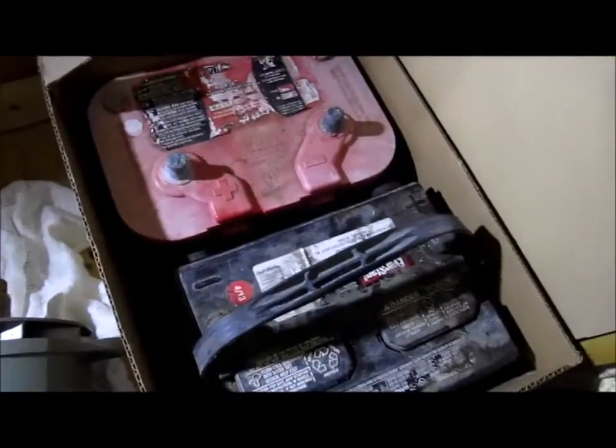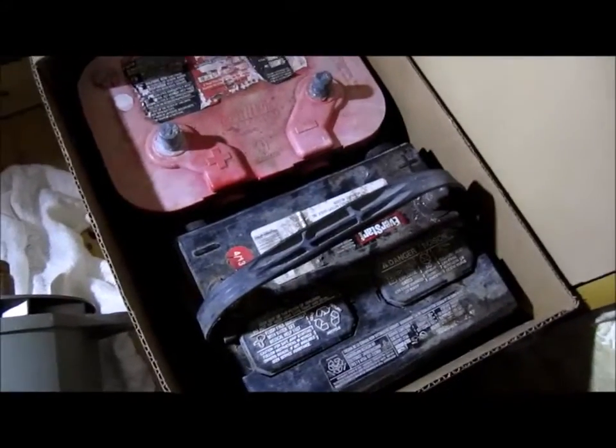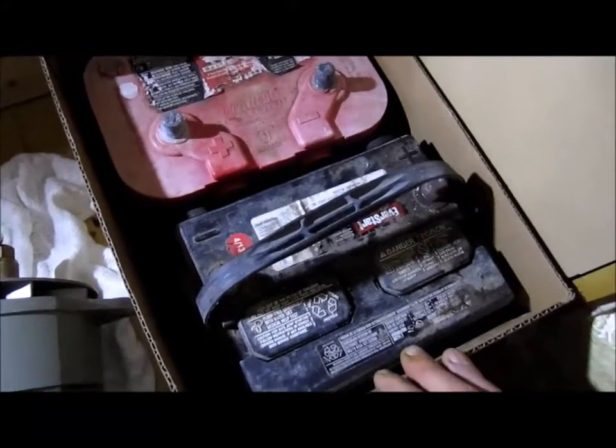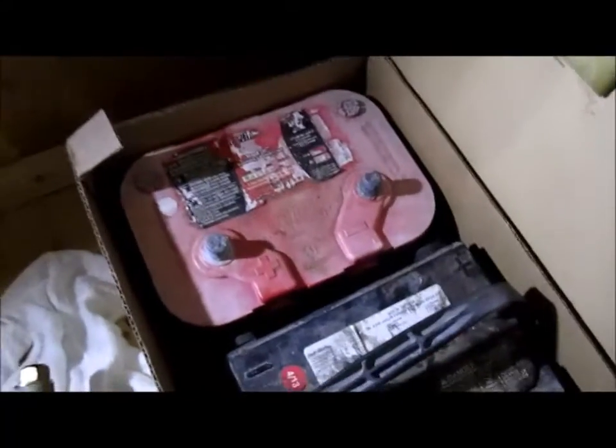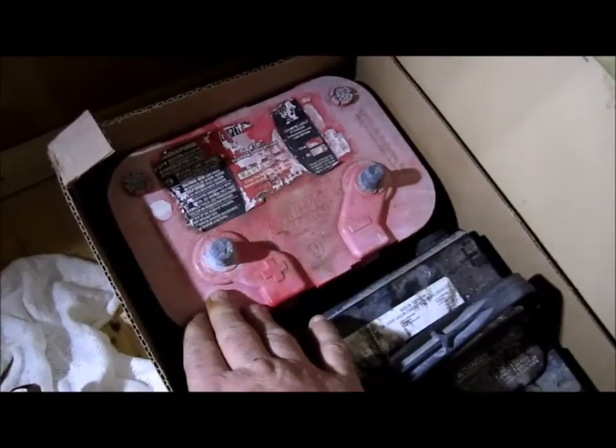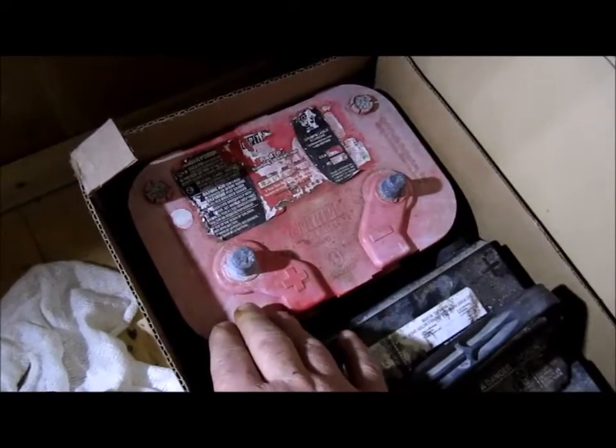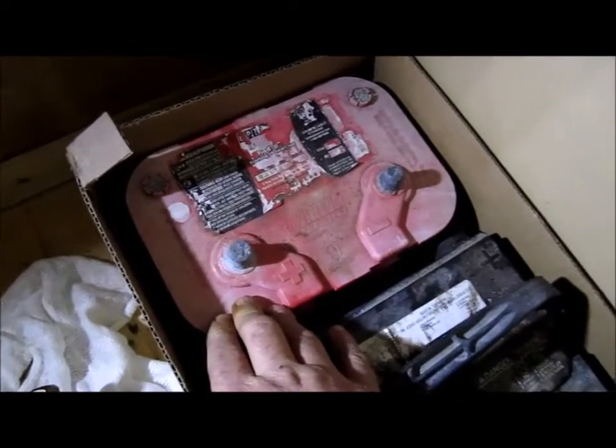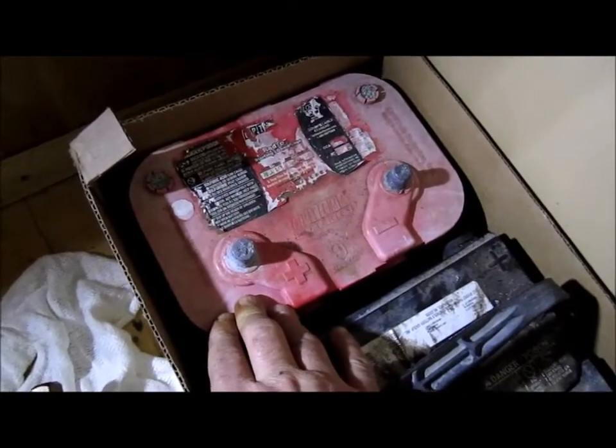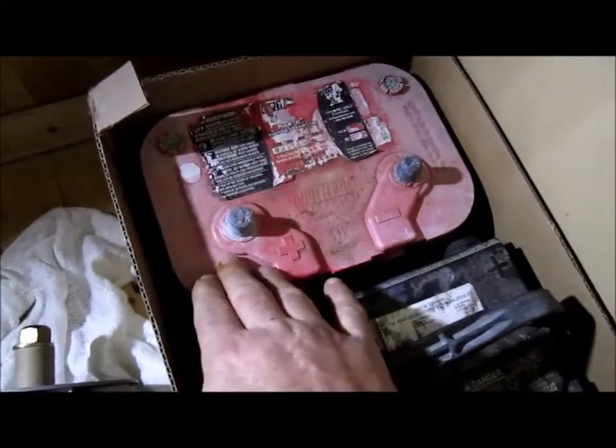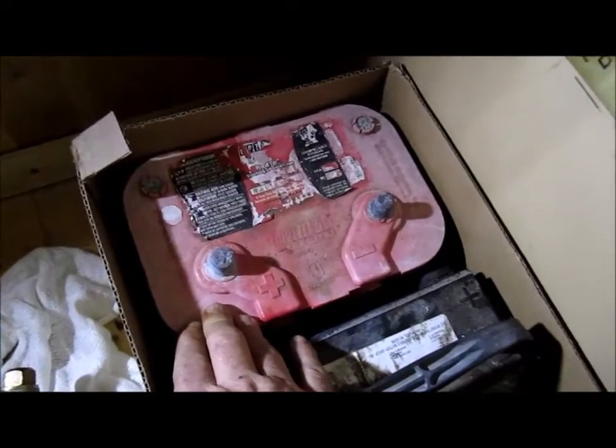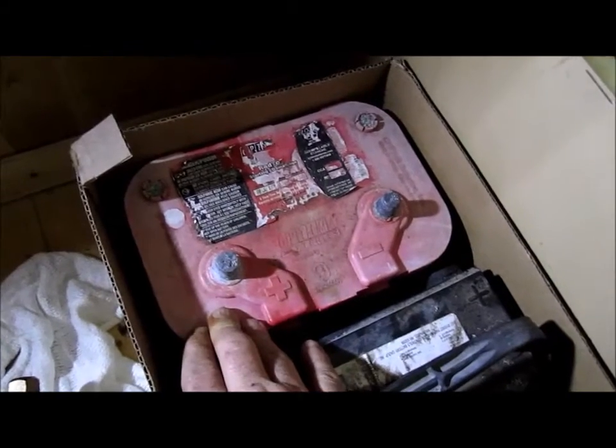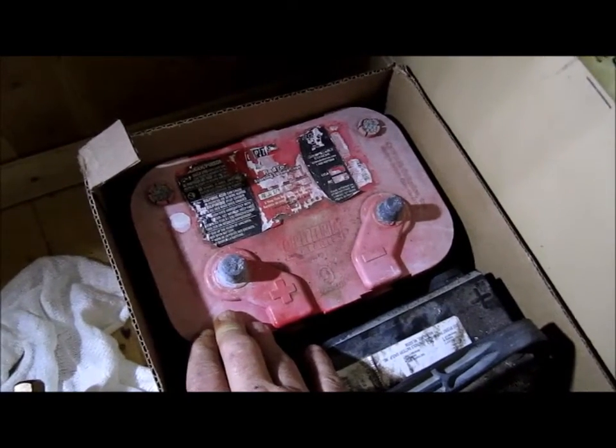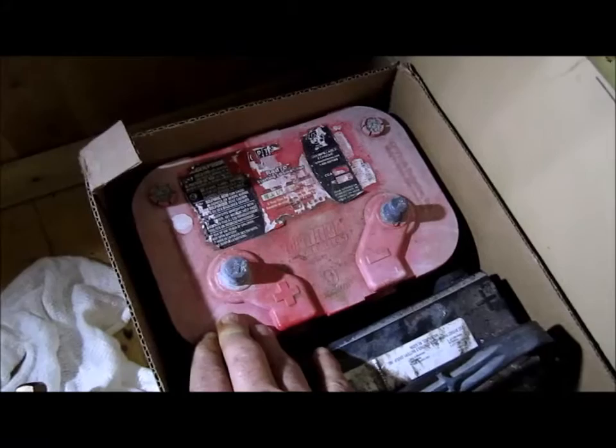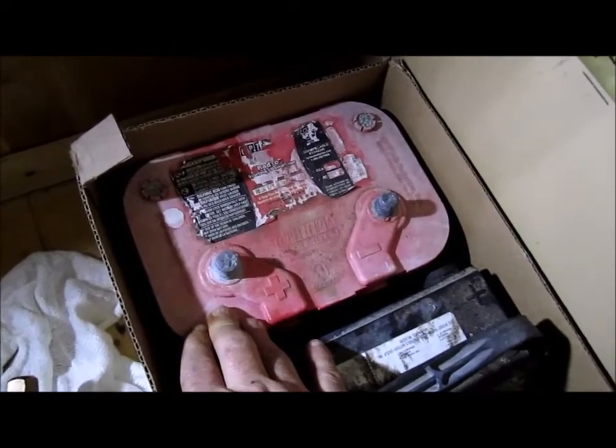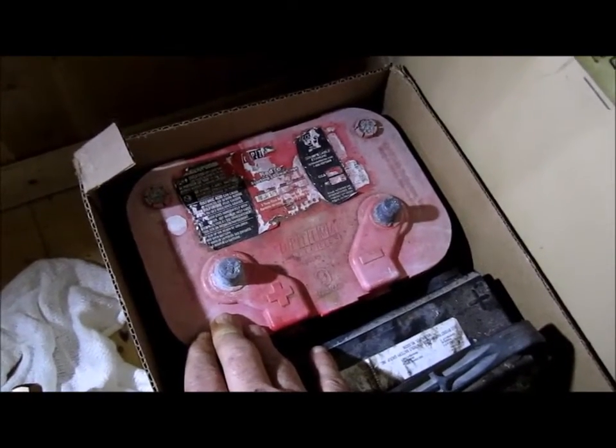Now the charging of such batteries, the high-end voltage definitely makes a difference. For example, for your AGM type batteries, I believe the high-end voltage is about 14.4 volts. That's the maximum. If they start going any higher than that, the cells, having no liquid inside, end up drying out. Then one of your cells goes bad, or two of your cells go bad, and before you know it, your battery's bad.